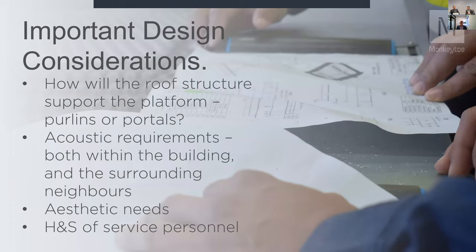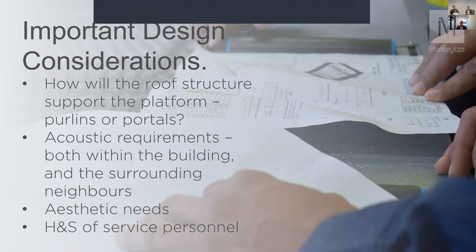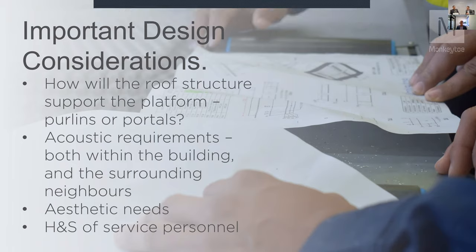Design considerations include: how will the roof structure support it — through the purlins or back to the main structure portals? Acoustic requirements, both within the building for occupants and for surrounding neighbours — particularly with noisier, larger air handling units. Aesthetics needs, whether there's a screening requirement. And obviously the health and safety of service personnel — if they're up there fairly often, we really need to consider their needs to keep safe.